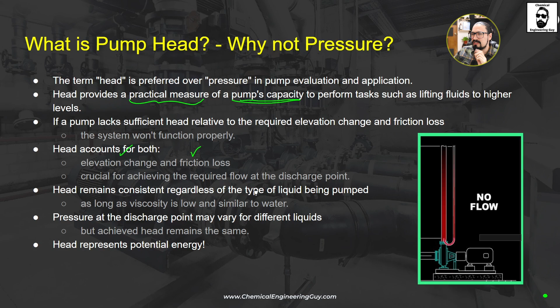And finally, guys, pressure at the discharge point may vary between different liquids. This is the most important part. Depending on the density and viscosity of the fluid, you're going to have several pressure differences. And this is the main issue. You are not going to be able to change the fluid or compare different fluids between the pump capacities, which is in many cases very important because you have a fixed pump and you're just asking yourself, maybe you're working with a sludge that varies its density or viscosity. It is way more straightforward to simply adjust the specific gravity rather than to recalculate everything in order to get the calculations for the second properties.